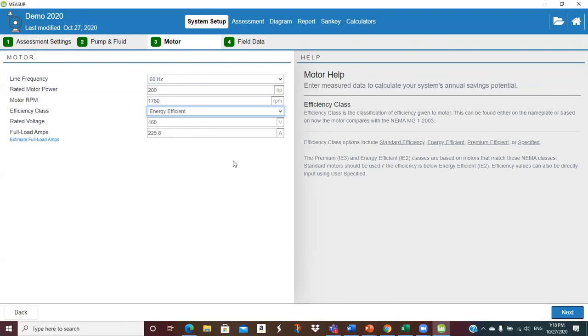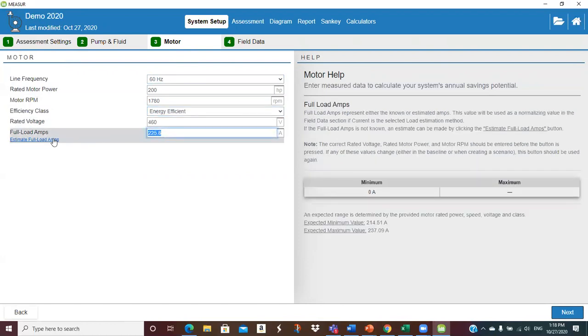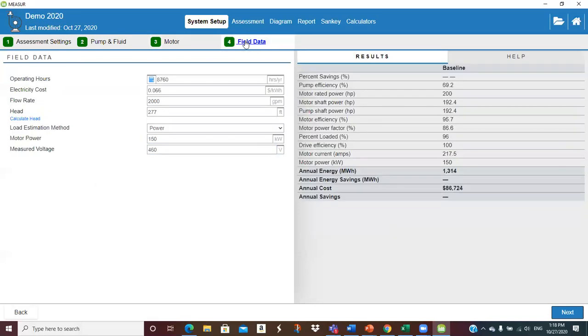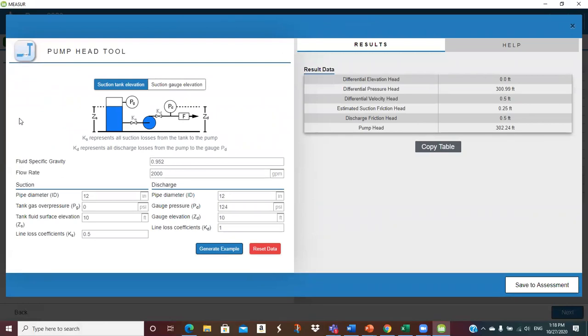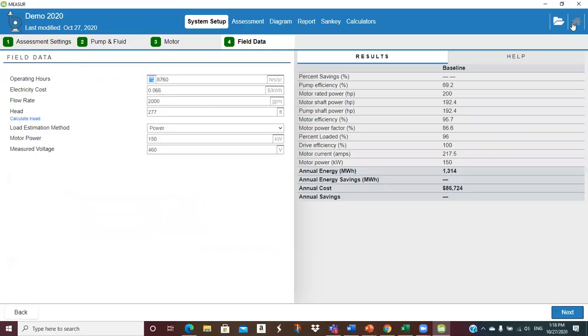This is just motor. This isn't field data. And you can estimate your full load amps somehow. I guess that is the estimate of the full load amps. Okay, and then your field data. This is what you measure out there. Electrical cost, same thing. Flow rate. Head, here's your head calculator. And guess what? It looks pretty much just like the other head calculator. Then we can measure kW or we can measure current, just like before. Put in your measured power, put in your voltage, bingo. And right there, with operating hours of 8760, it estimates the annual cost of operation.